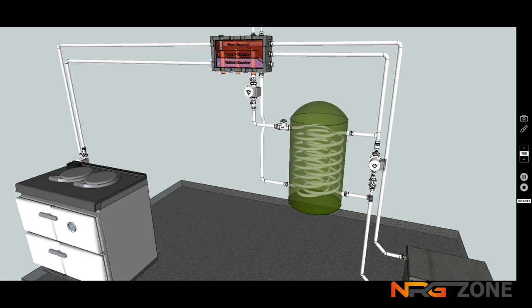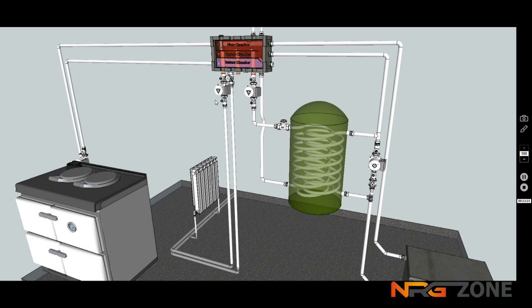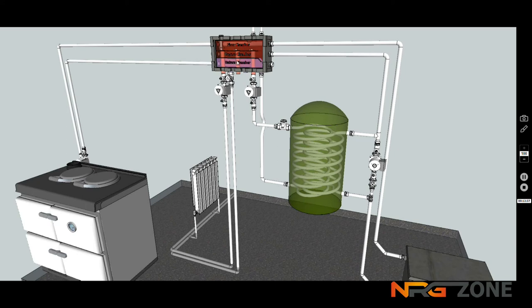So now, now we have our boilers connected, we can introduce zones. For example, if we put in a radiator zone, very simply what we would have is a pump from this connection, the left-hand connection, which connects onto the top chamber, pulls the hottest water down around our radiator circuit, back around again, and the return water passing through a non-return valve is collected in the return chamber.